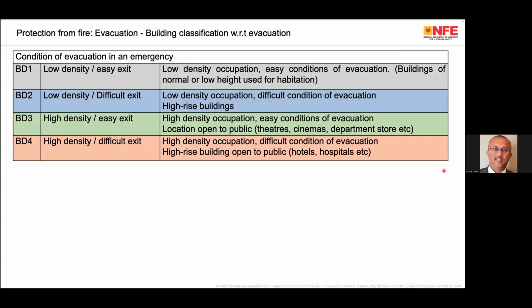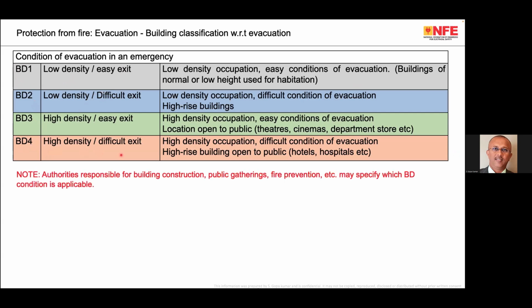One concept included in the standard is with respect to the condition of evacuation during emergency. With respect to evacuation, the electrical installations are classified into 4 types: BD1 to BD4. BD1 low density easy exit, BD4 high density difficult exit. Here, the recommendation from the National Electrical Code or from the IS 732 is that authorities responsible for building construction, public gathering or fire prevention may specify which BD condition is applicable for a given building. So it is the responsibility of the fire department to tell that, okay, this building more than this much size, I categorize into BD1, BD2 or BD3 and BD4.